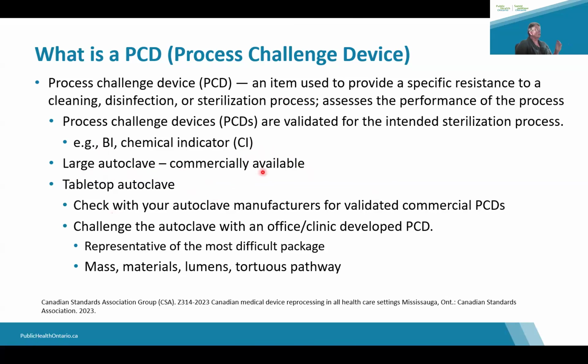So for large autoclaves, commercially available PCDs, that's the norm. For tabletop autoclaves, depending on which autoclave you have, there may be a validated commercial PCD available, but you would have to check with your autoclave's manufacturer regarding that. Because of that, you can make up your own PCD, and it's really important that when you make this PCD, it represents the largest challenge that your autoclave would meet during the course of the day. So representative of the most difficult package.